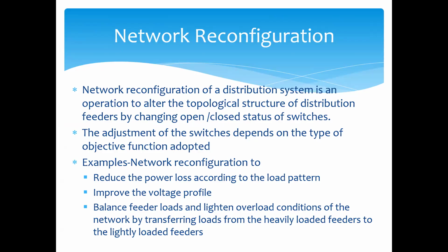If you can remember, at the beginning I showed you the distribution network structure. There were several switches along the ring and even in the radial network. What we can do is change the open or closed status of those switches. For what? The adjustment of the switches depends on the type of objective function adopted. For what objectives do we operate those switches? For example, we do switching or network reconfiguration to reduce the power loss according to the load pattern, to improve the voltage profile, and to balance feeder load and lighten overload conditions of the network by transferring load from the heavily loaded feeders to the lightly loaded feeders.